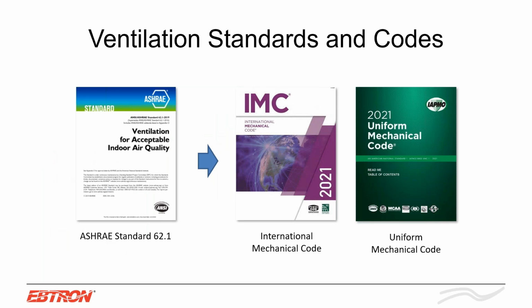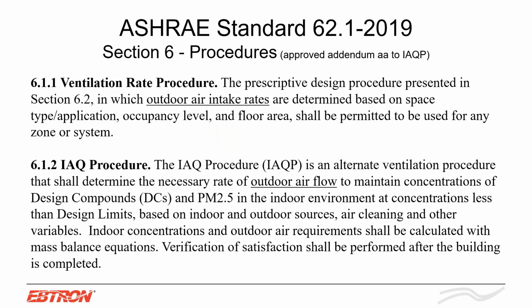And let's take a closer look at ASHRAE 62.1, because basically there are two separate procedures that you can design to as a consultant engineer. You have the VRP, which is the ventilation rate procedure. This is a prescriptive design procedure where the outside airflow rates are determined based on space type, occupancy level, and floor area. And this is what you typically see a lot of engineers designing to.